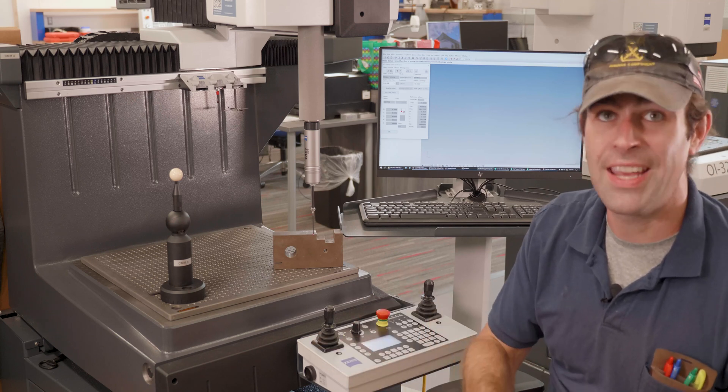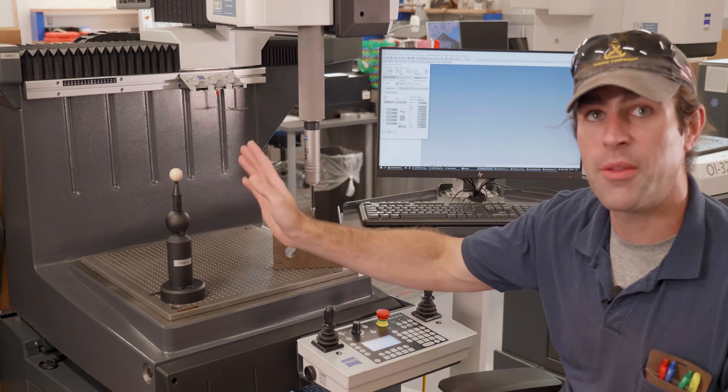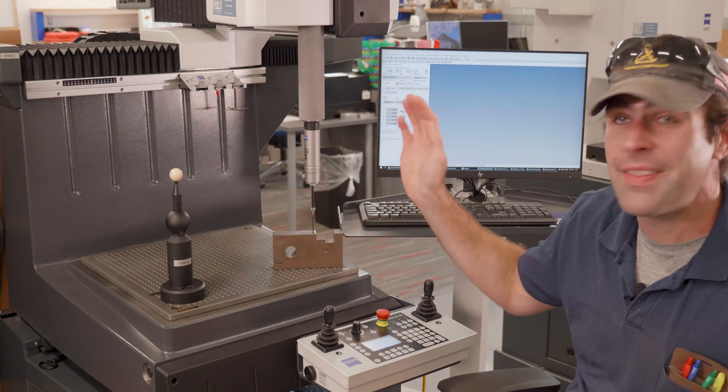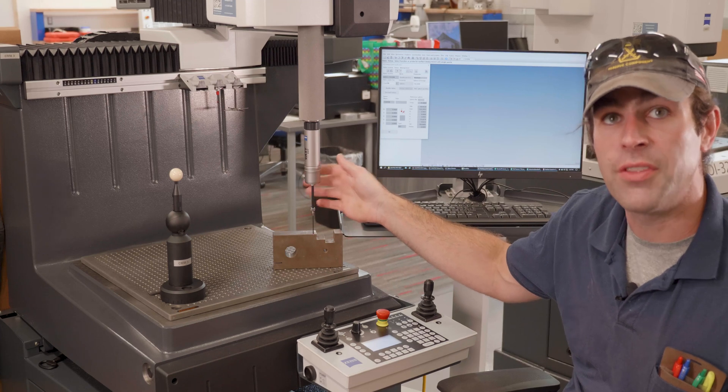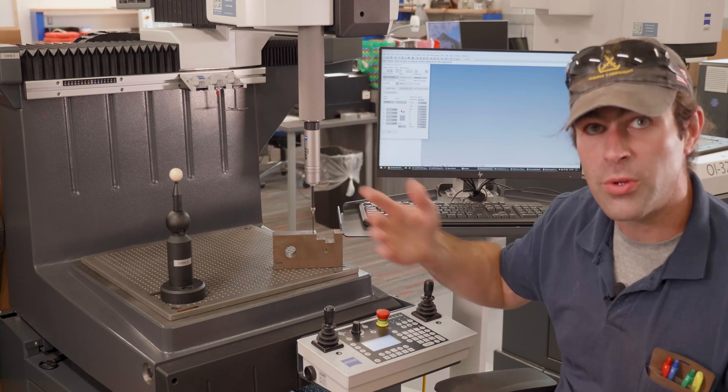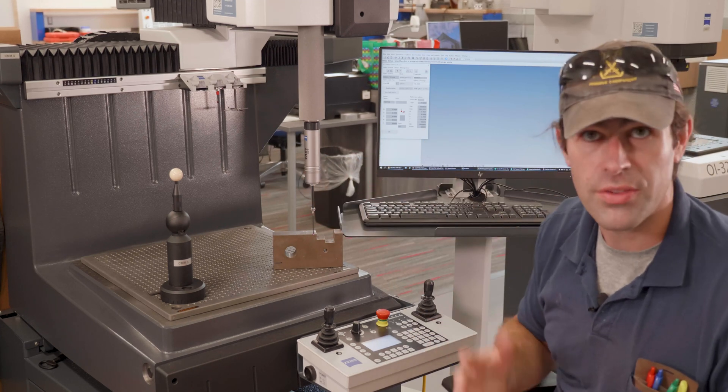The computer is going to take the information from the reference sphere and the master probe, which are known, and then find out the unknown of this probe through the qualification program. So let's hop right into that.